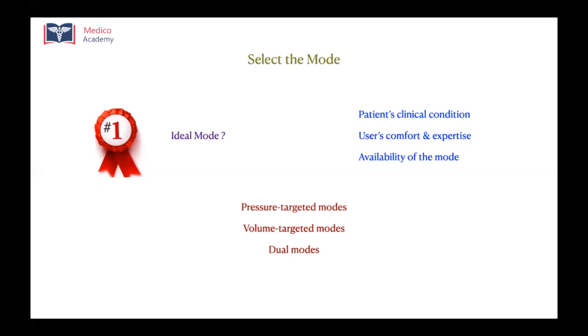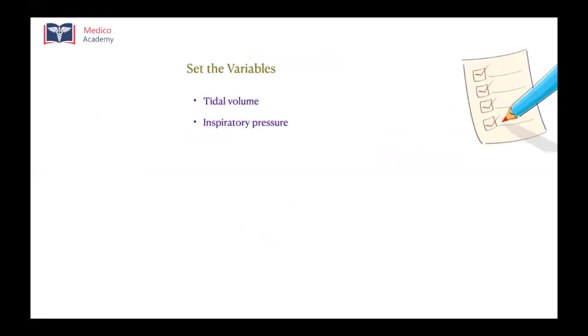Once you select the mode, your screen pops up and you will see multiple variables. What are the variables that you usually set? I'll be talking only about the basic variables that you'll be needing. In advanced modes, you will have different kinds of variables, very fine settings and everything, but I'll be talking only about the basic variables. So, tidal volume and inspiratory pressure. If it is a volume targeted mode, you'll have to set the tidal volume. If it's a pressure targeted mode, you have to set the inspiratory pressure. If it's a dual mode, you may have to set both.